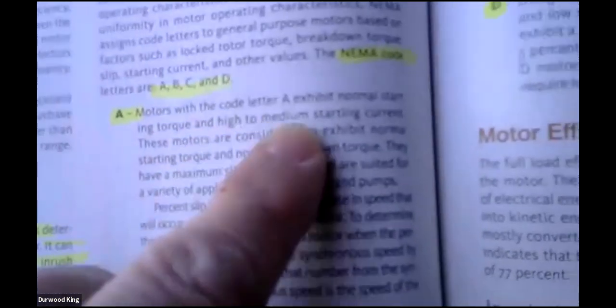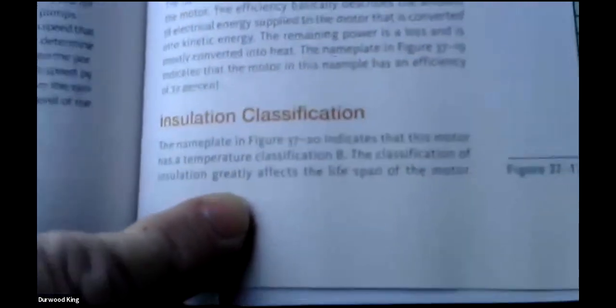It says motors with a code letter A exhibit normal starting torque and high to medium starting current. If you have a NEMA design code of B, they're most common, they exhibit high starting torque and low starting current. If it's a C, they have high starting torque, low starting current. If it's a design D, high starting torque and low starting current. Again, that's information that's actually on the nameplate. That's your design, and whoever's picking the motor would be the one dealing with that. And then your insulation class, that's important if you're dealing with really hot areas like around ovens. So insulation class is, I go back to screen share.